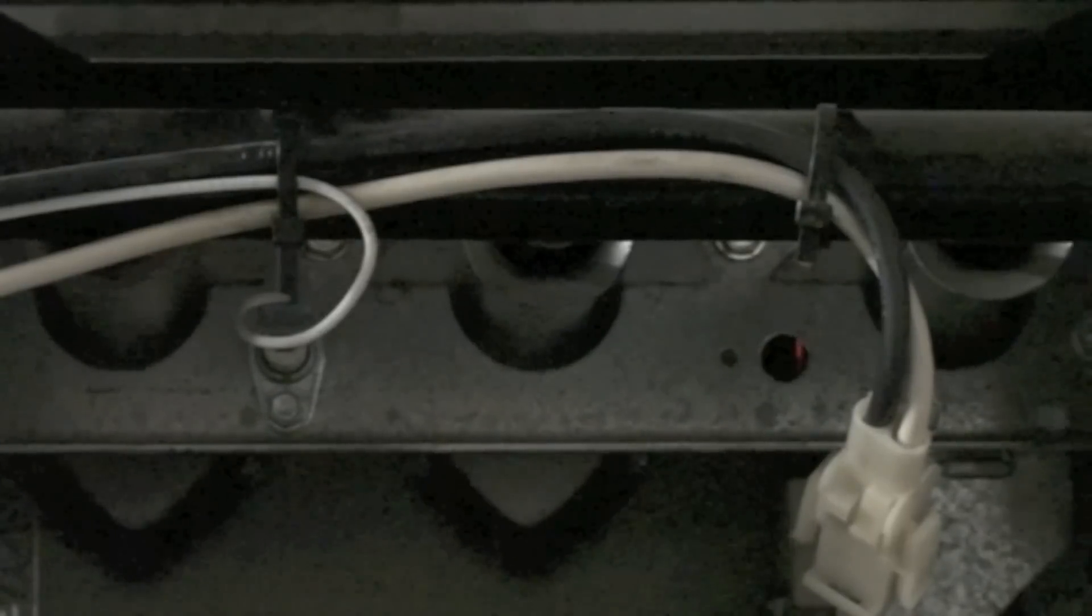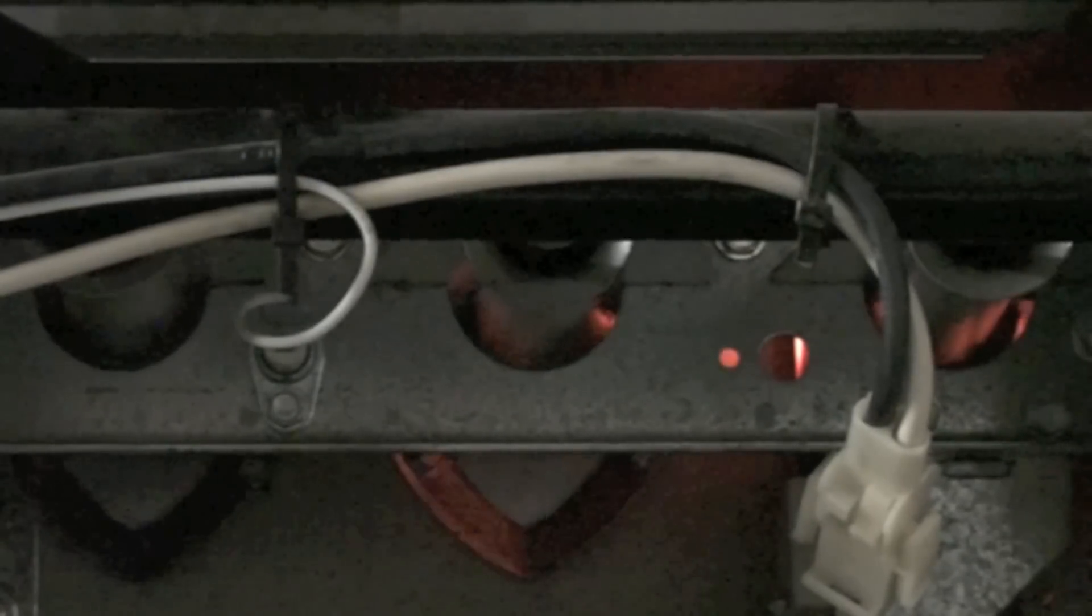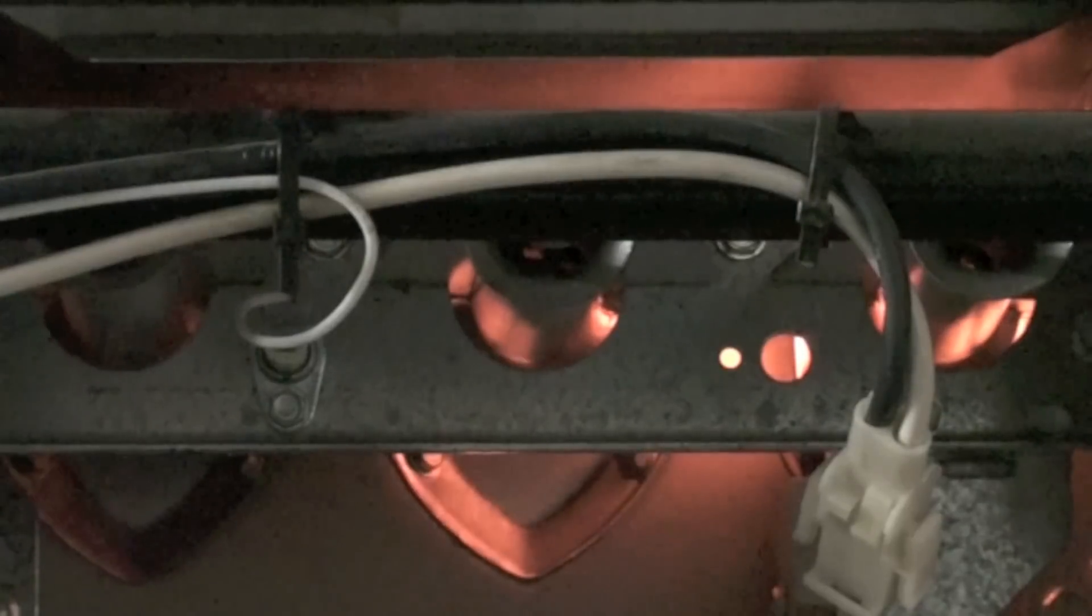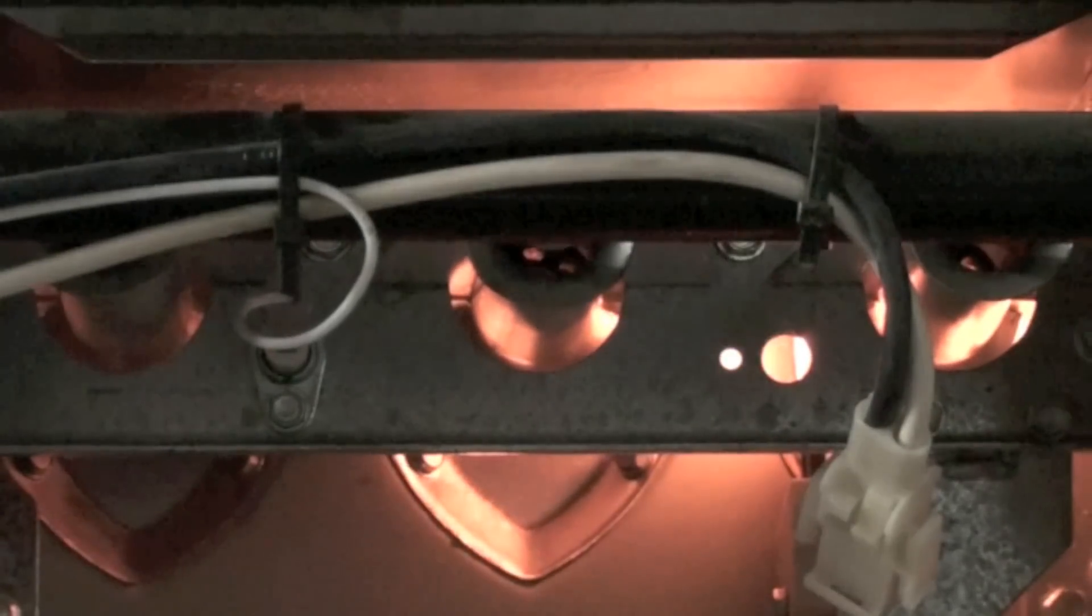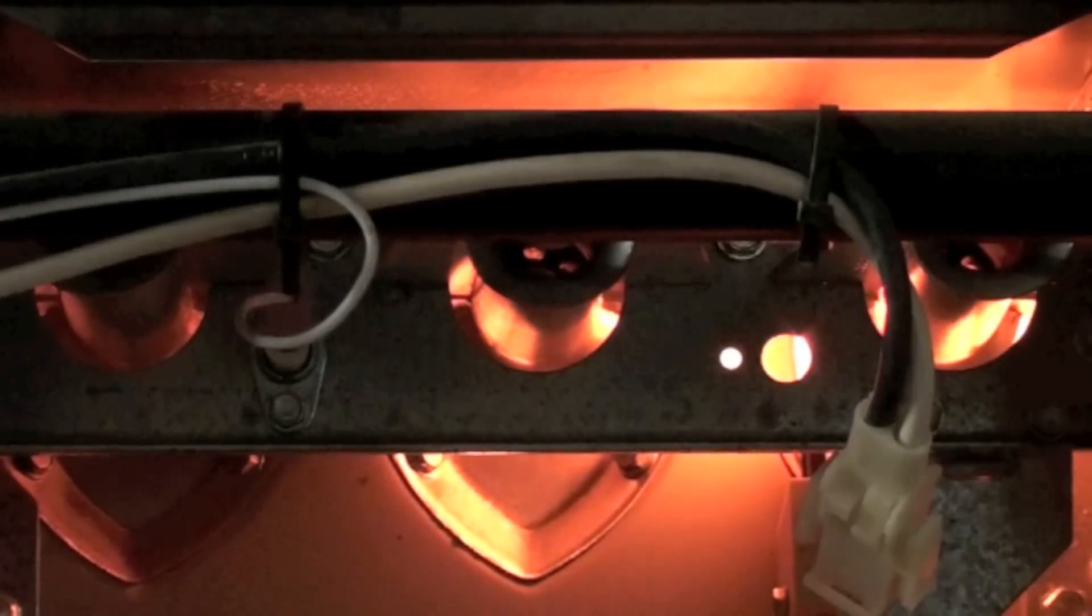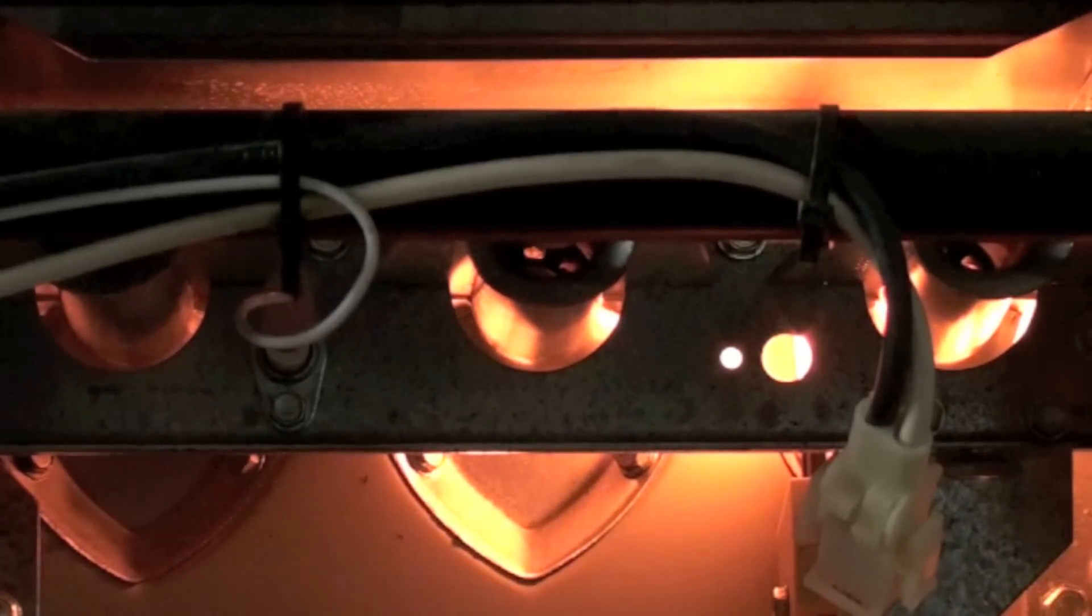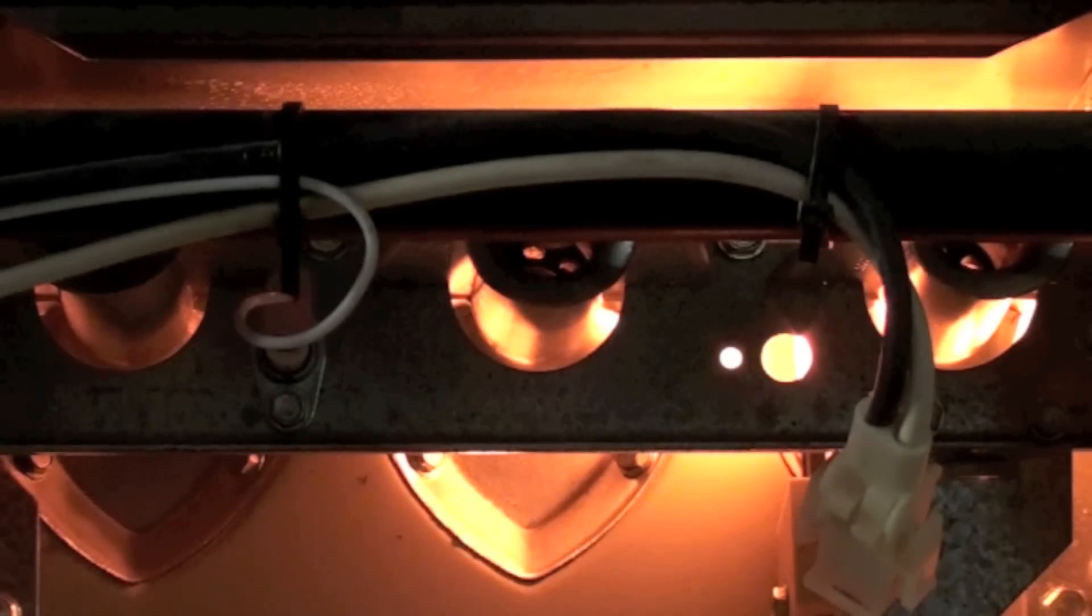Now I'm going to fire this thing up and we'll see how it acts. Okay, we're going to fire this thing up and under normal conditions you can see the hot surface igniter come on on the right there and pretty soon the burner is going to come on and it'll stay on.